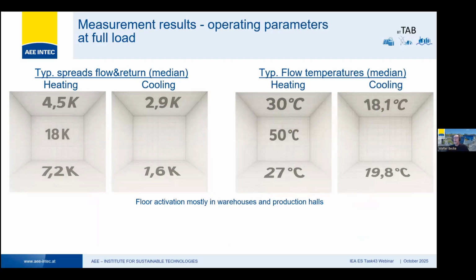You see typical spreads between flow and return temperatures at full load for heating and cooling on the left side of the slide, and also divided between those different activated components. So for heating, if heating is done over the ceiling, then the typical spread between flow and return temperature is about 4.5 Kelvin. For the floors, it's a bit higher, and for the wall, it's even higher. The reason is that for the walls, you have the existing wall and you have to apply tubes from the outside. Then you have to make sure that the heat coming in the tubes passes through the existing wall into the room. So you usually need higher temperatures to achieve that, which you can see on the right side.